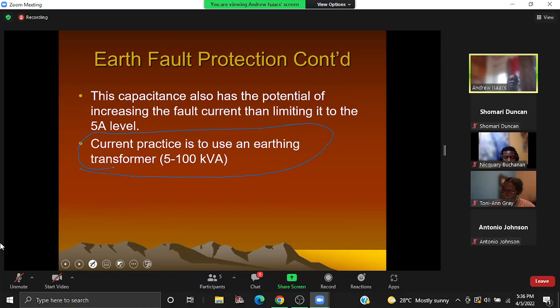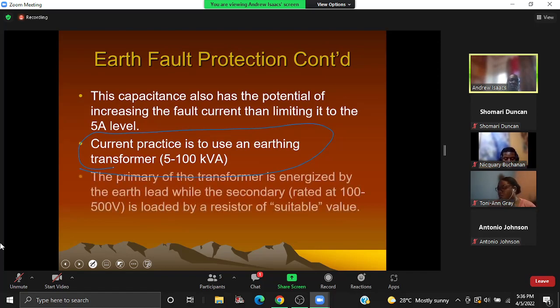So, in using the earthing transformer, the rating of the transformer, as we said, is between 5 and 100 kVA. And the primary principle is that we are going to have a transformer whose primary is energized by the earth lead.